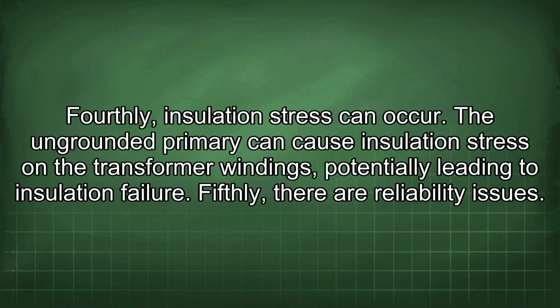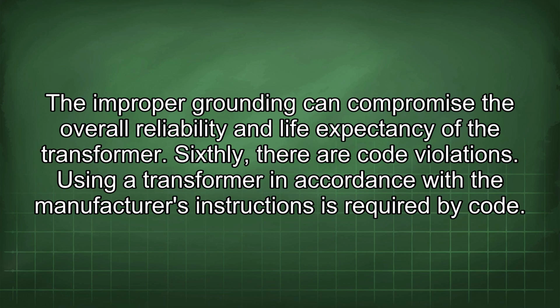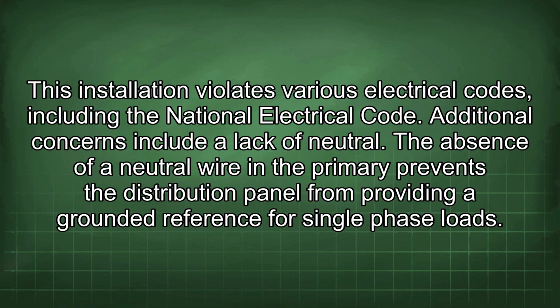Fourthly, insulation stress can occur. The ungrounded primary can cause insulation stress on the transformer windings, potentially leading to insulation failure. Fifthly, there are reliability issues. Improper grounding can compromise the overall reliability and life expectancy of the transformer. Sixthly, there are code violations. Using a transformer in accordance with the manufacturer's instructions is required by code. This installation violates various electrical codes, including the National Electrical Code.